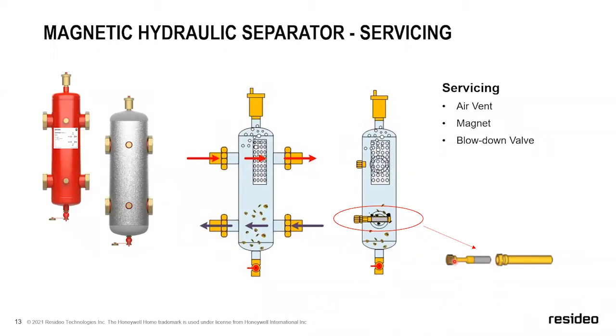So you unthread the magnet, pull it out. What's going to happen is all the ferrous metal that's stuck here on the well is going to drop out and fall down once you unthread that magnet. Then you're going to take a bucket. If you want to run this to a drain, great. I never really see them run to a drain, but you can. Most people will just grab a bucket or even like a large cup and just put it under here.